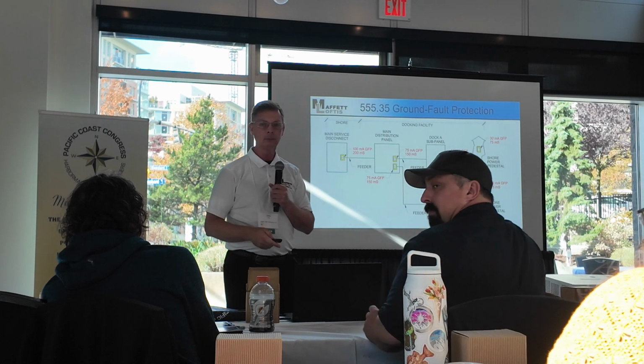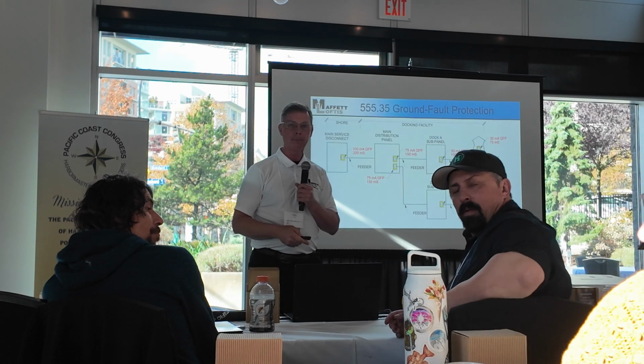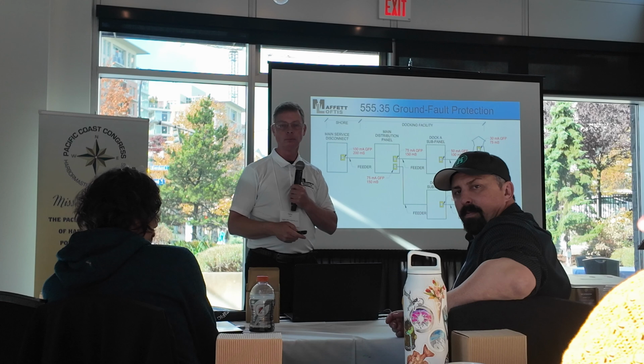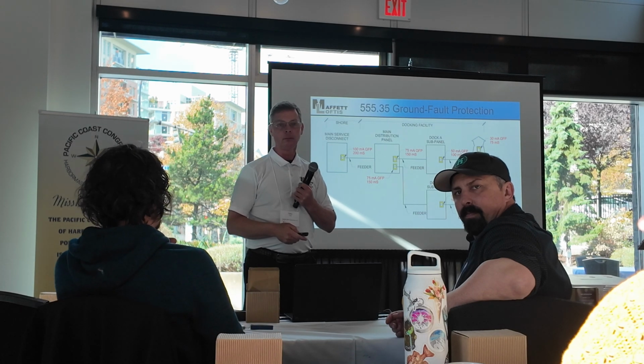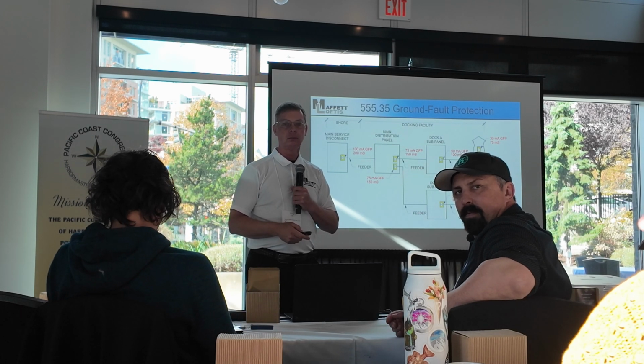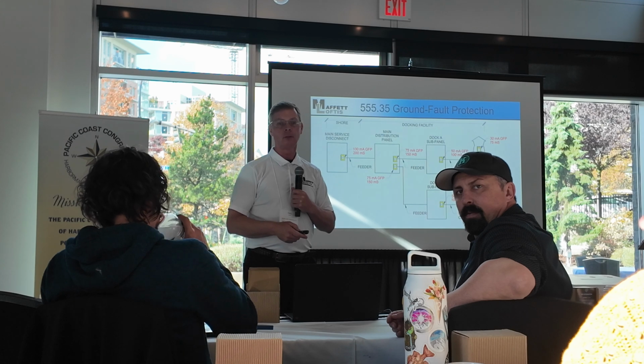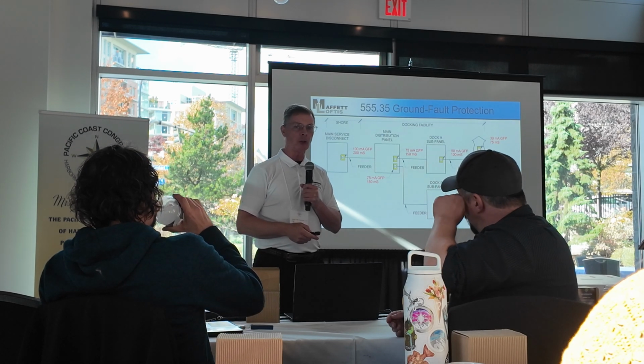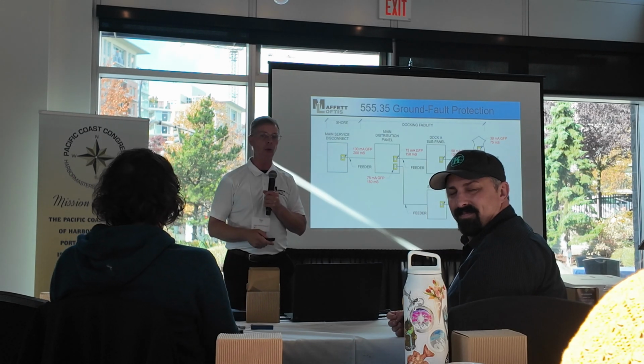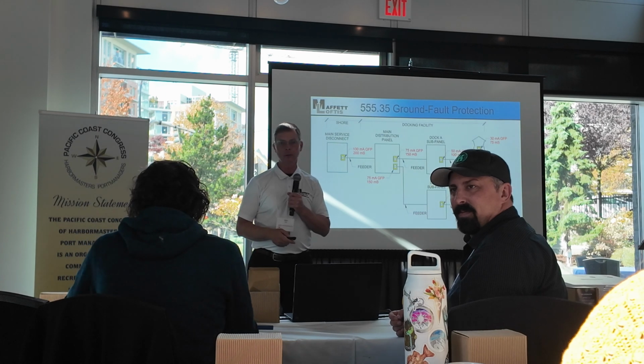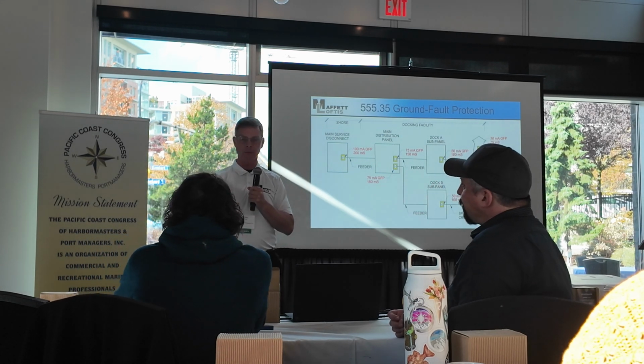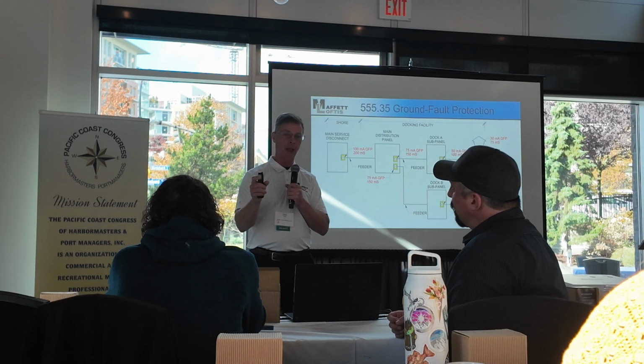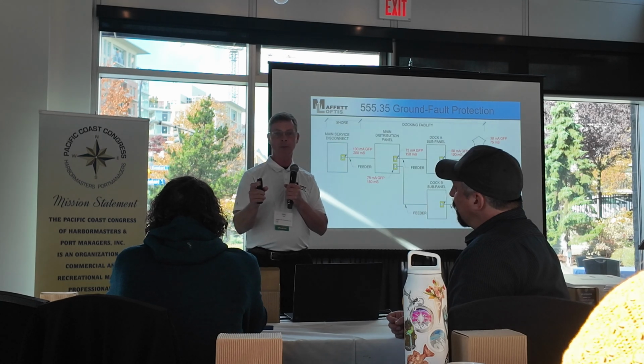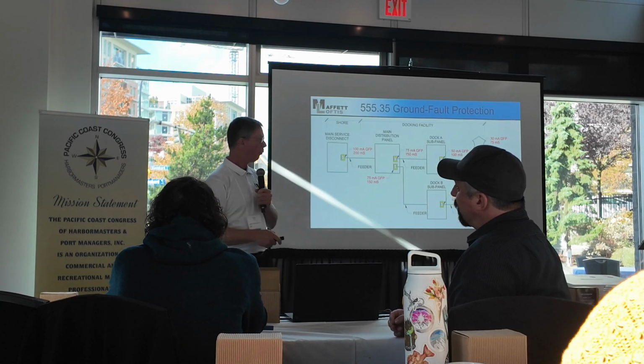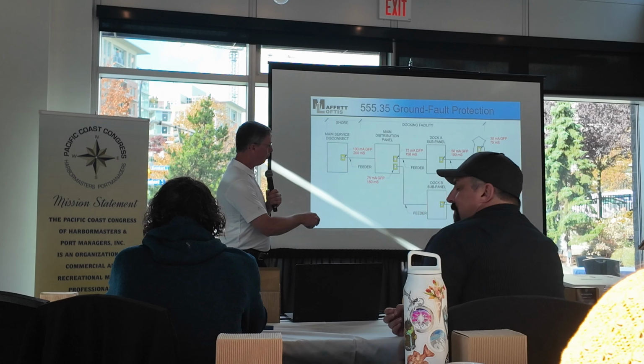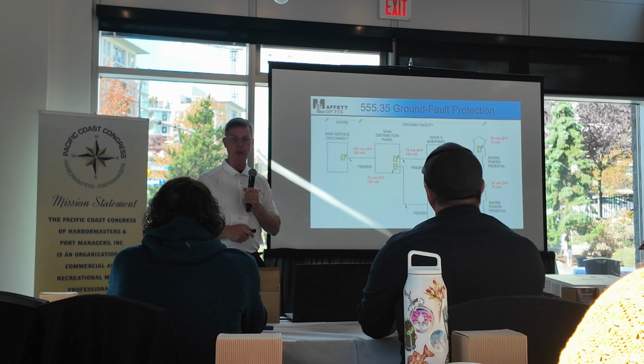Yes, sir. Are those coordination trip settings customizable from the marina's perspective, or is that something that the manufacturers take care of? Generally, the manufacturer. It depends on who you use. Right. There are some devices out there that are factory burned in as far as the trip level and the trip times. There are some that can be field settable. Right. And for this one, I don't mind it being factory burned in because it's set at 30 milliamps.